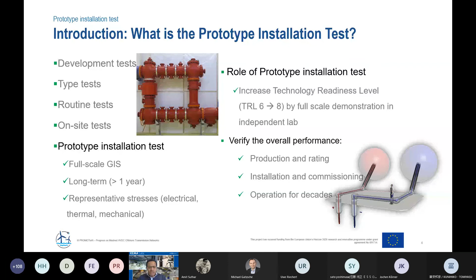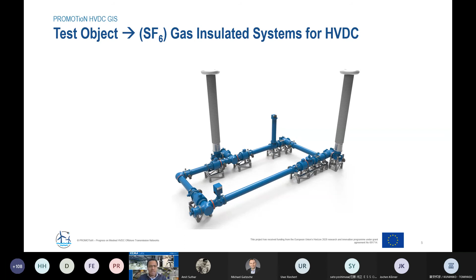Well, the test object itself is SF6 gas-insulated systems for HVDC. Here you see a photo of the test object from our laboratory. Well, this will be explained later by Michael in detail, of course. Just to give you some information here, a total length of about 31 meters of bus bar is involved, including different shapes: straight, L, T, and X shapes. And it has been divided into 8 partitions.